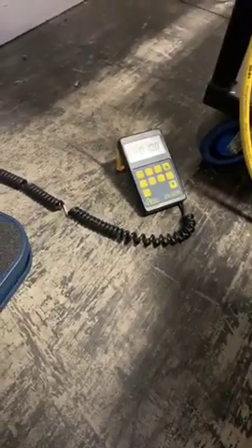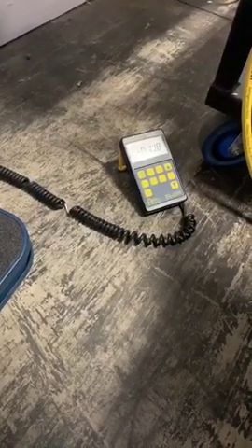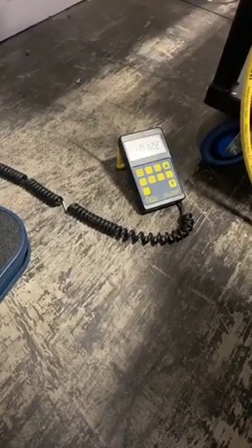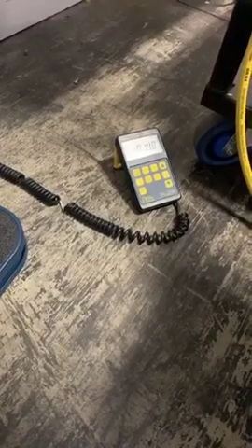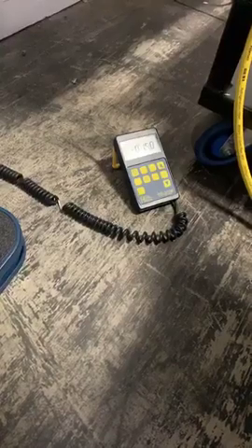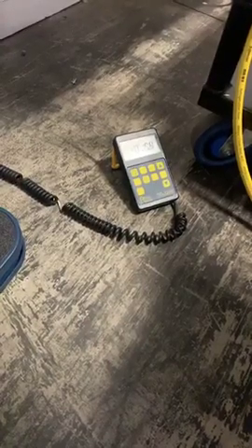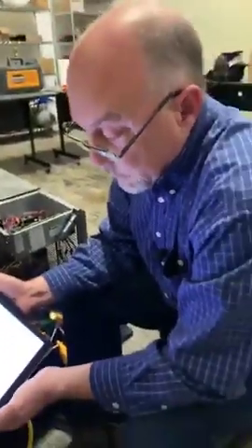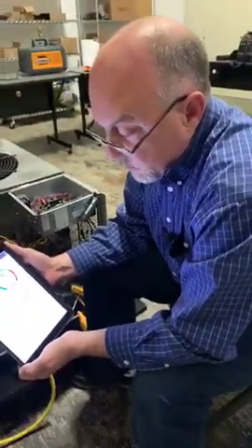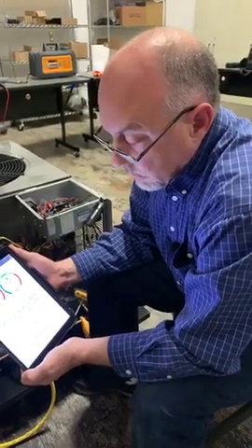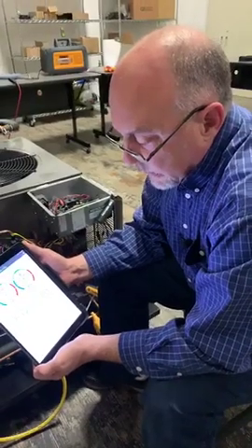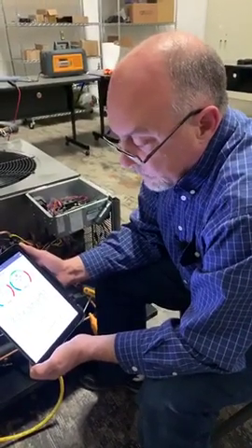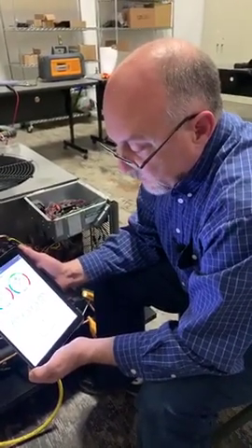What's cool is the reason we're adding a pound in here is because this system is a 1.5 ton system. It's all based off of the size of the system and the percentage of refrigerant charge that we want to add based upon how far it is off the target. So if this was a 10-ton system, we might be adding in 10 pounds of refrigerant or something, being this far off the target. So all the algorithms determine how much refrigerant we need to add based on how far we are off the target, and as things start falling into line.